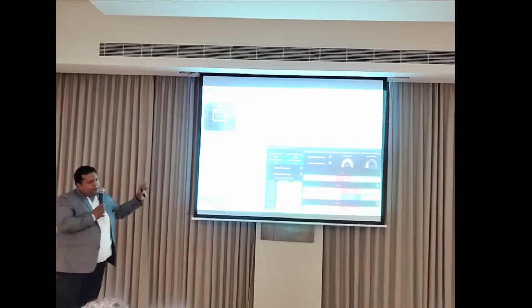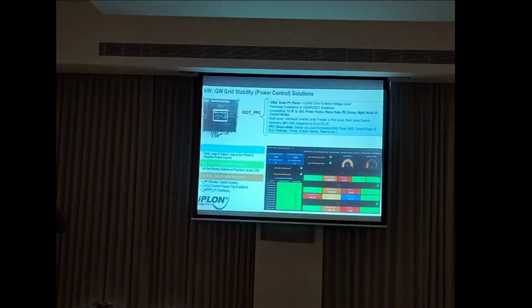This power control isn't only at the plant level—we also have the ability to scale it down to feeder level, plot level, or individual inverter level. With the IGOT PPC, we can also interface to telemetry over IEC 104, so that in future SLDC or NRLDC can give control commands directly to the power plant. This is similar to what's happening in Germany now with Redispatch 2.0.